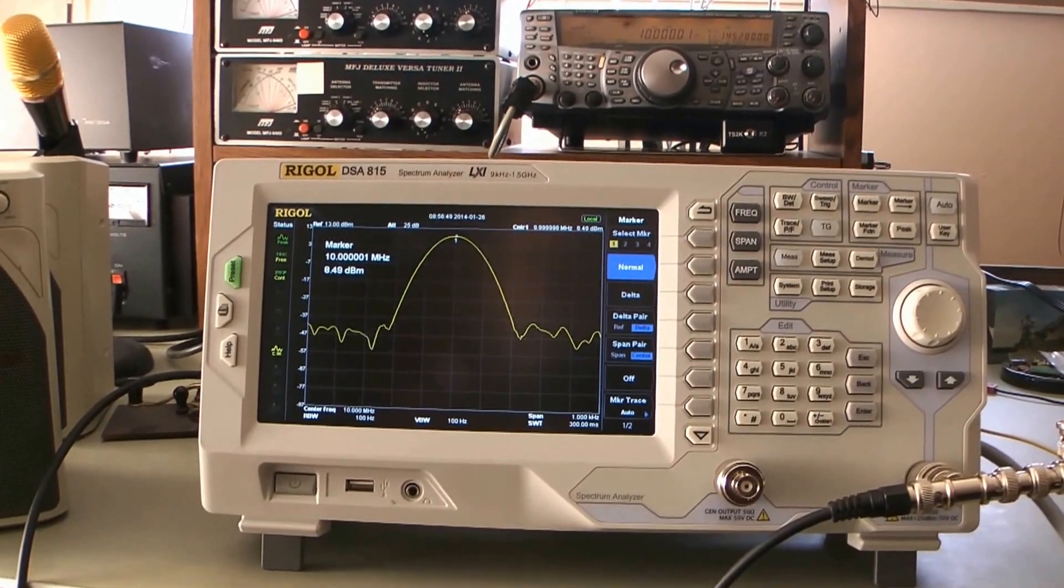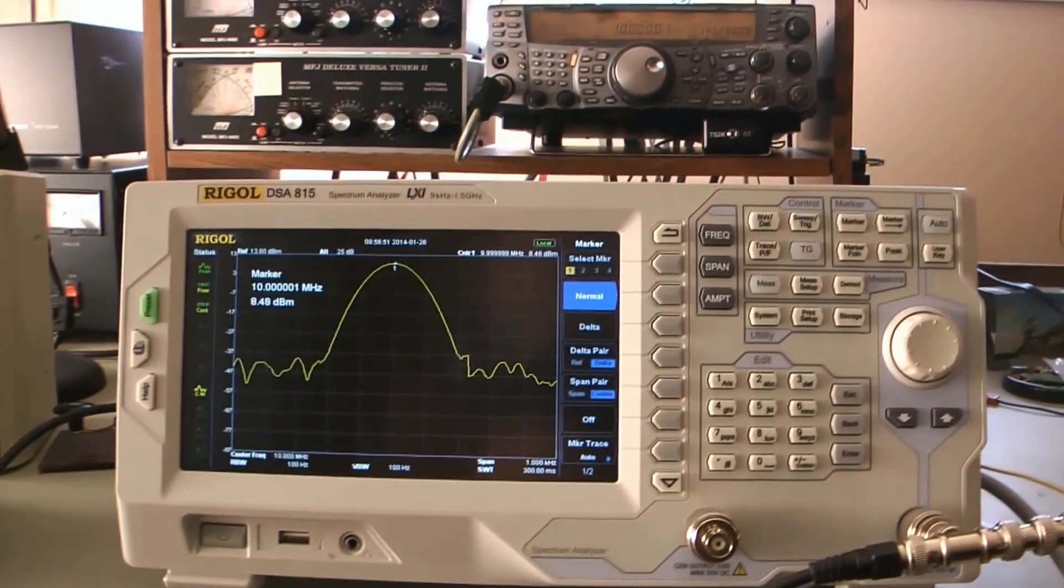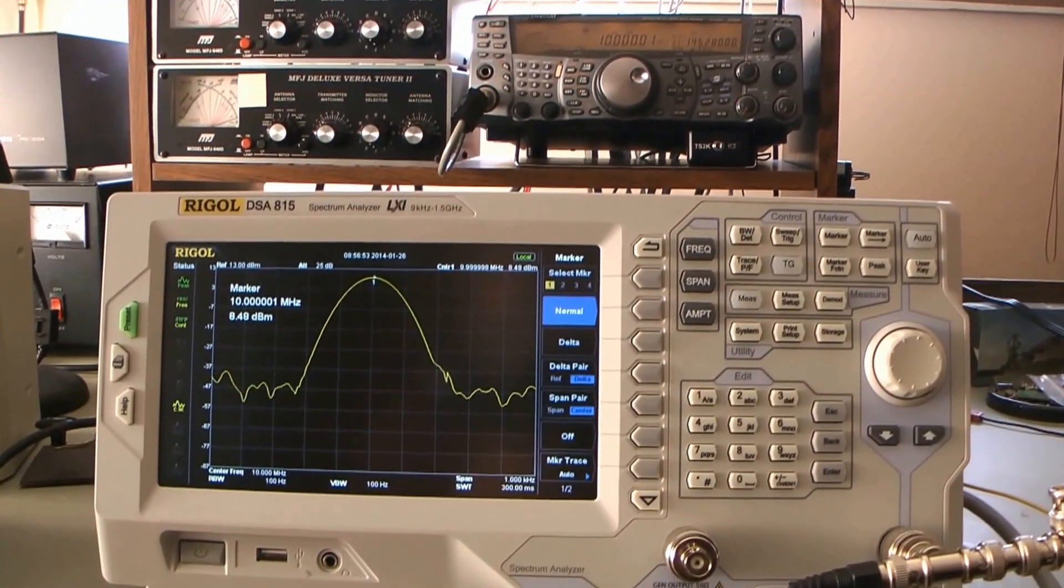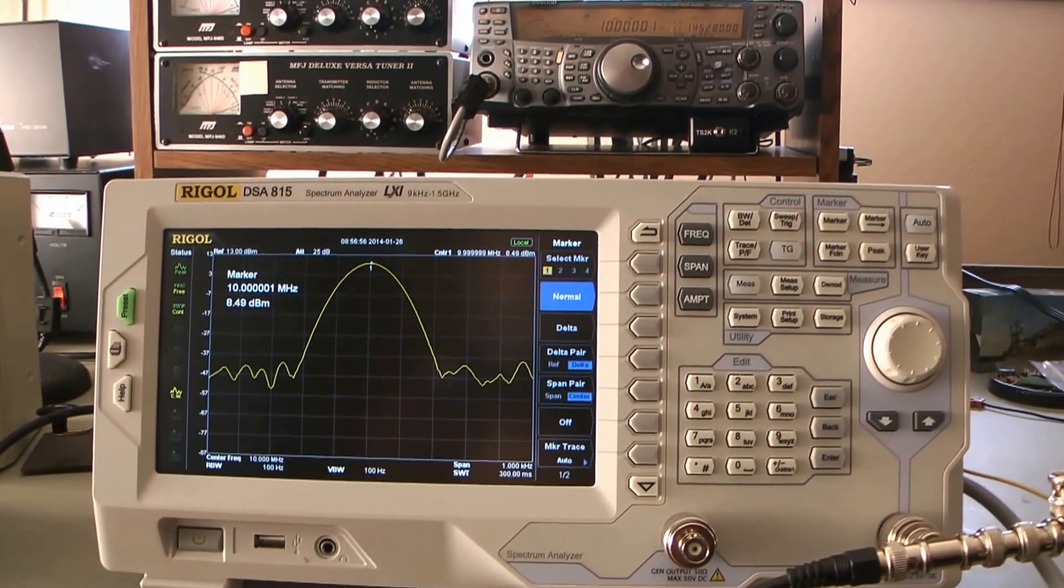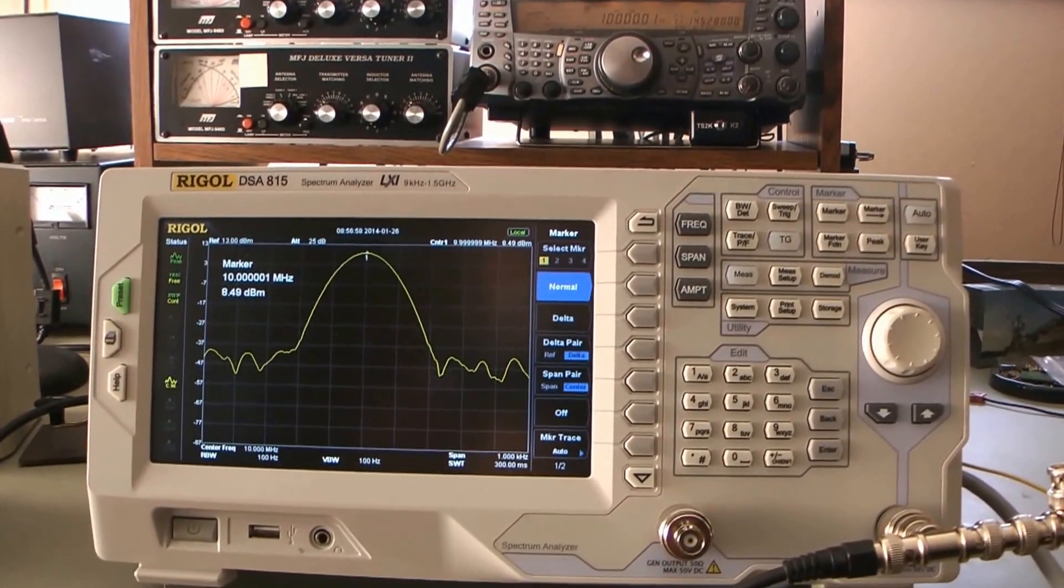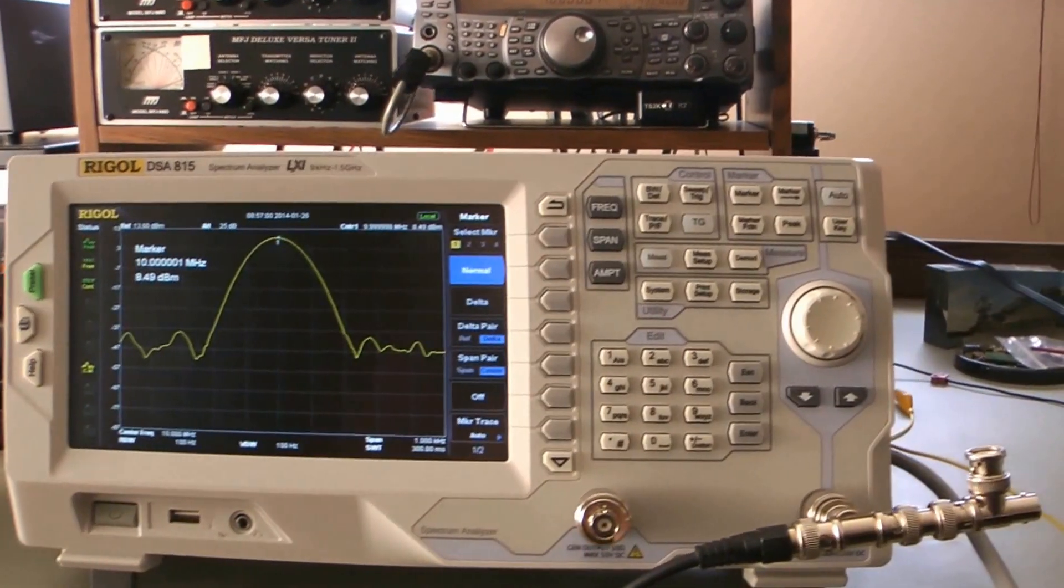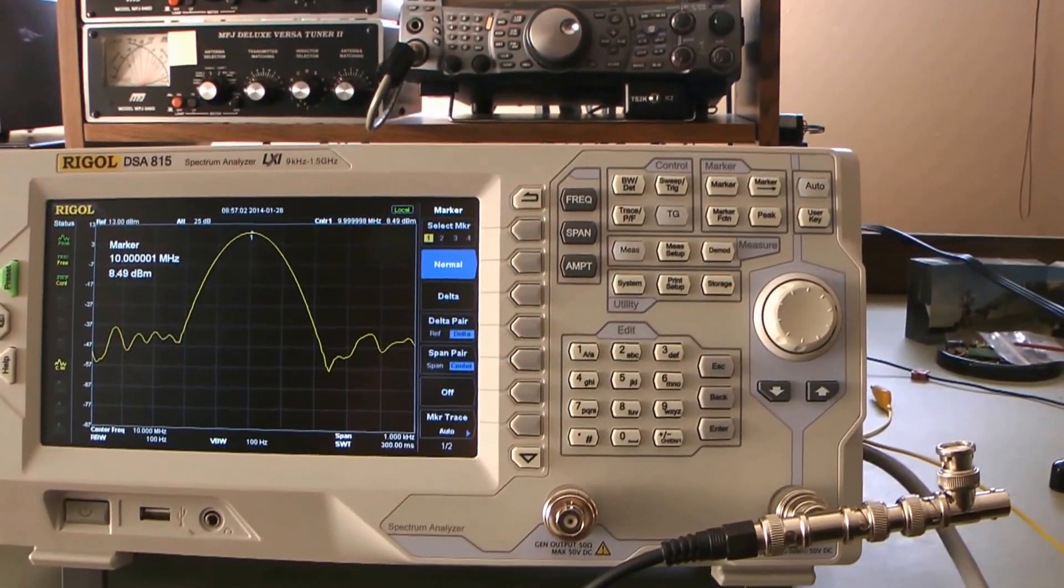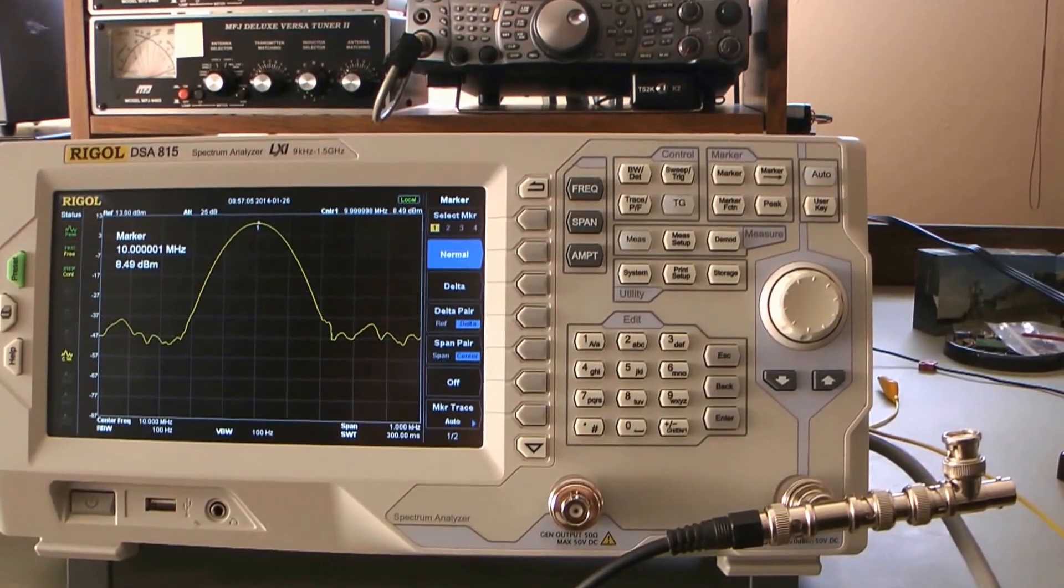So first a little bit about the setup. What you're looking at is the signal from the 10 MHz output port on the back, and then that's just feeding the signal generator. That's not really important for the calibration, but just so that you can see.